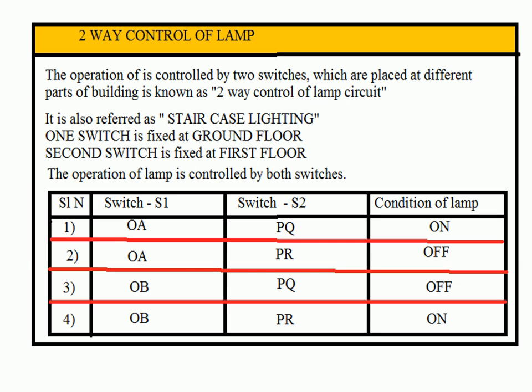In the same manner, the operation of a lamp is controlled by two switches, S1 and S2. You can see there, we have already discussed two positions. In this manner, logically, it may operate in four conditions. When the lamp is on, the circuit is closed. When the lamp is off, it is an open circuit, that you remember. Hence, there is no limitation to only two-way control of a lamp.